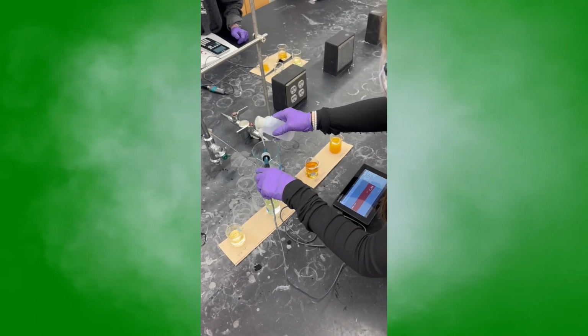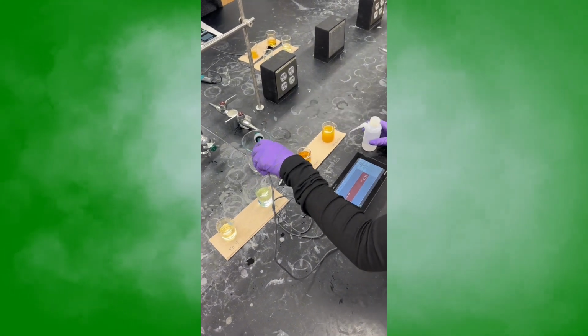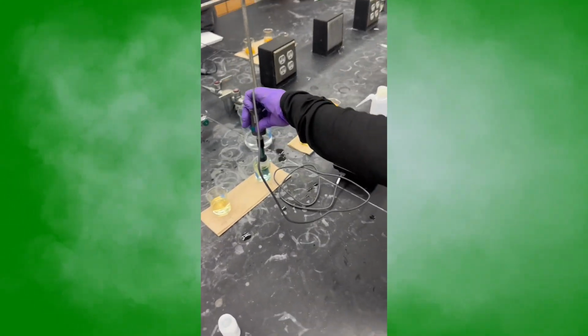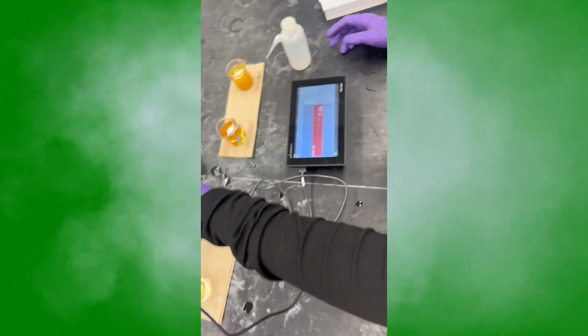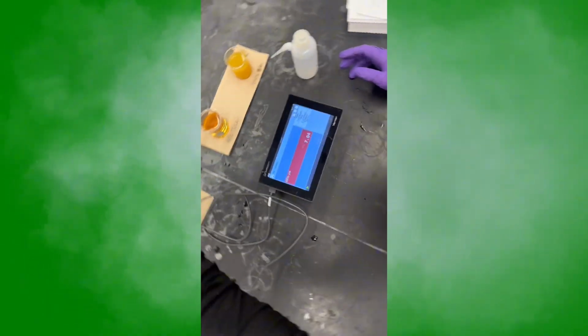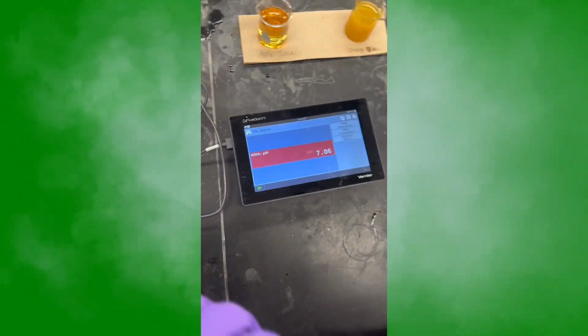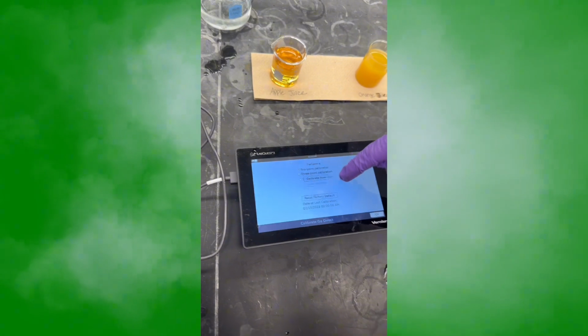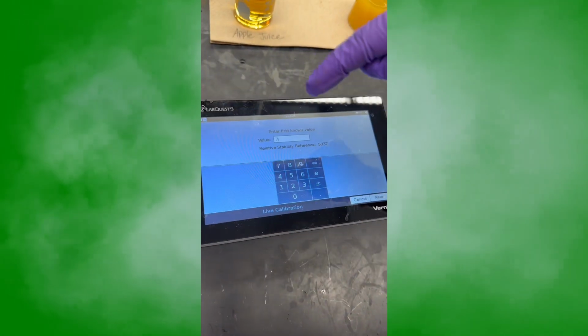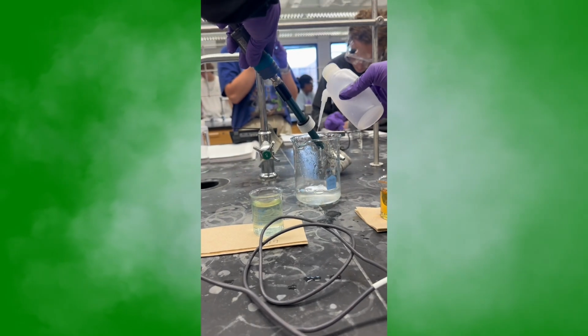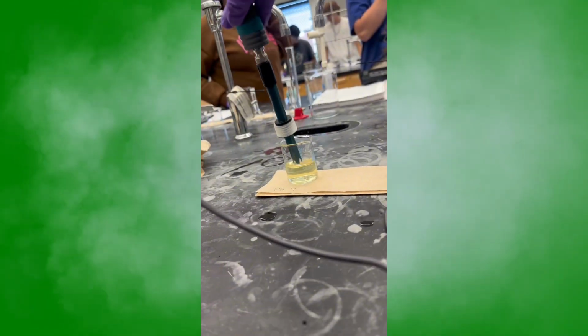Make sure you're using the 2-point calibration method when we test our two buffers. The buffers in question will be pH 7 and pH 4. pH 4 is used for acidic solutions. Take the electrode out of the storage and rinse it with distilled water over a waste beaker. Then place the probe into the pH 7 buffer, press sensors, and then calibrate. Type in 7, corresponding with the pH, and then press keep.